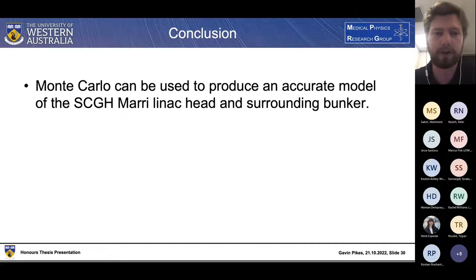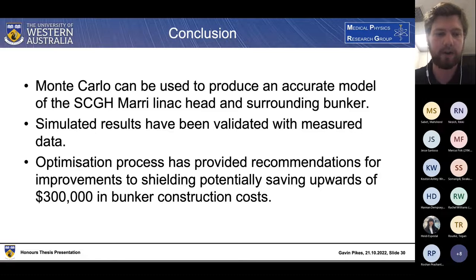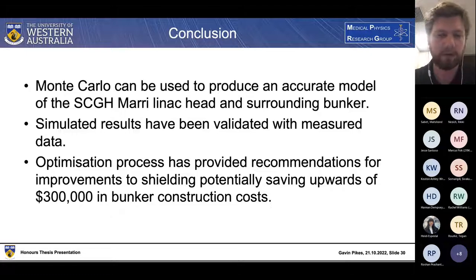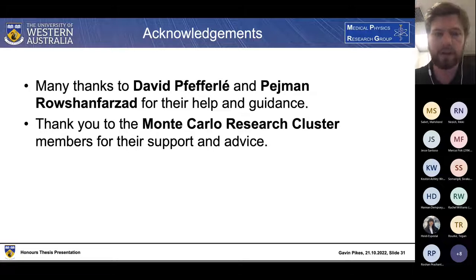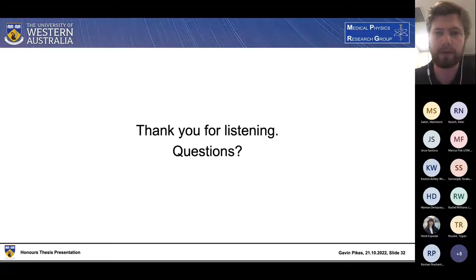In conclusion, Monte Carlo simulations can be used to produce an accurate model of the Sir Charles Gairdner Hospital Marri linac head and surrounding bunker. The simulated results have been validated with measured data, and the optimisation process has provided recommendations that can potentially decrease bunker construction costs by over $300,000. I'd like to thank David and Pejman for their help, and also the Monte Carlo Research Cluster members Marcus, Marsha, and James for their support and advice.